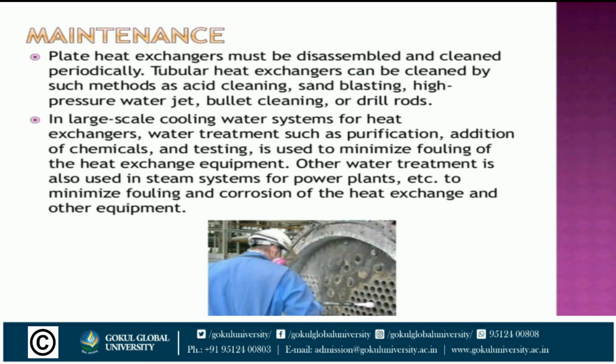Again, maintenance of heat exchanger. Plate heat exchanger must be disassembled and cleaned periodically. Tubular heat exchanger can be cleaned by such methods as acid cleaning, sandblasting, high pressure water jet, bullet cleaning or drill rods.